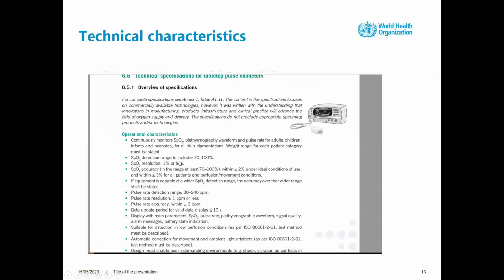We do have the technical specifications. For example, the SpO2 detection range should include 70 to 100%. The resolution should be 1% or less, and the accuracy within plus or minus 2% under ideal conditions. We know there are others that are 5% or so, but that is too much to make a really good assessment of the patient.